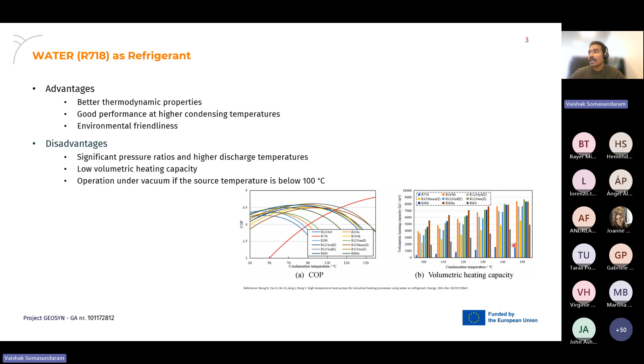In the graph shown below, we see how the COP of the heat pump using water as refrigerant varies. We can see it is an excellent refrigerant for condensing temperatures above 150 degrees centigrade. Further, the volumetric heating capacity of water also increases with increasing condensing temperature.